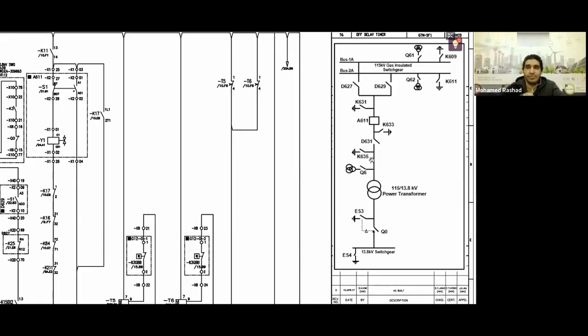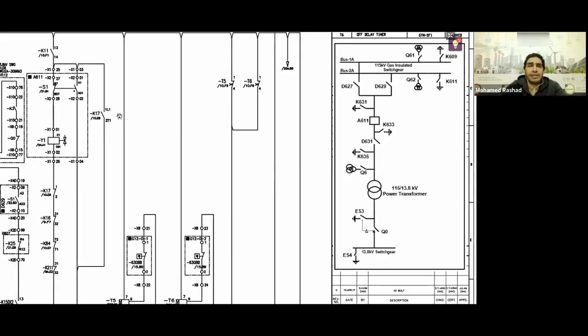If you are using a step-down transformer, I actually close the high voltage side first, then I close the medium voltage side, or what is referred to as the upstream, and then I close the downstream, right? So to close the breaker above in service, it must be ensured that the transformer is open from the other side. You must ensure the transformer is open, because if it is closed, the inrush current plus the no-load current will be drawn from it, and this will be incorrect for the transformer. So the conditions for the energization of the transformer are that we close the transformer from the upstream first, then from the downstream.